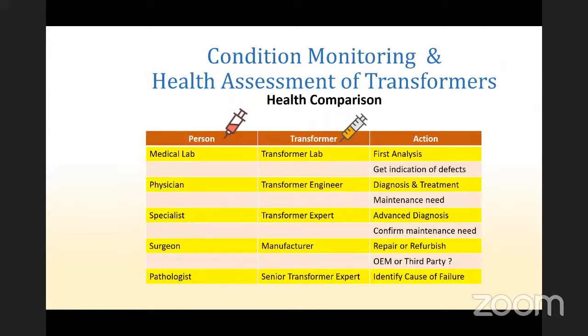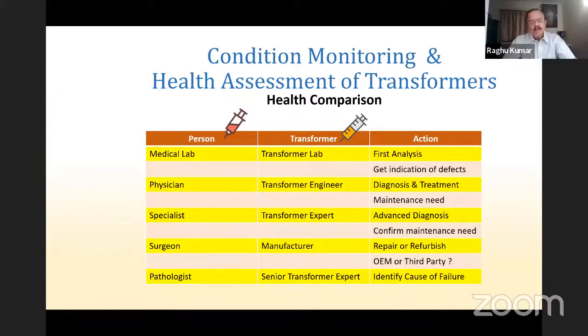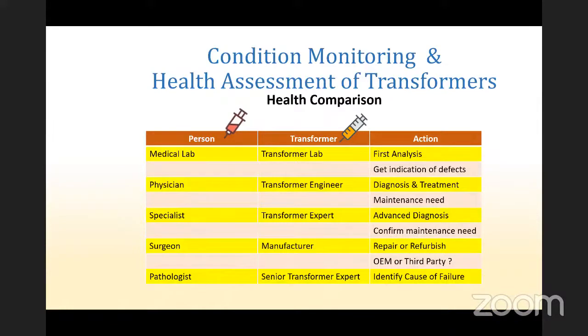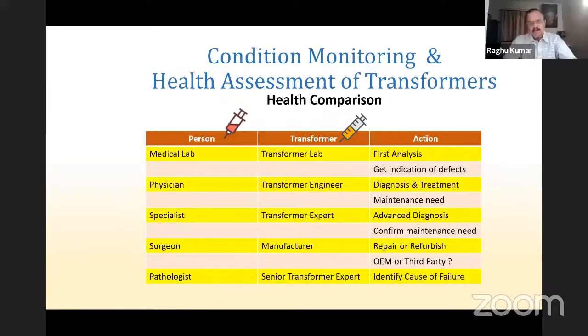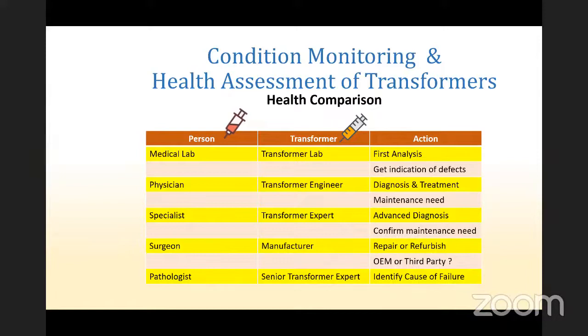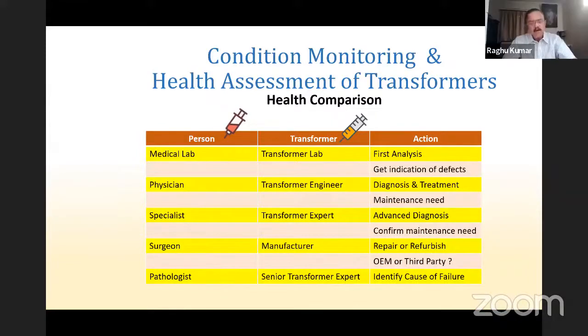And in the third stage, where you have to go in for an internal inspection or intervention, like what a surgeon does, we have to call in the original equipment manufacturer or a third party capable of doing this. Normally, the original equipment manufacturer is preferred since the third party can also do the job, but they will not have the required spare parts to do the repair work. And lastly, even with all the condition monitoring done, certain transformers do fail. And after failure, the pathologist's role is taken over by the senior transformer expert who removes the winding and does an internal inspection to find out what actually went wrong.